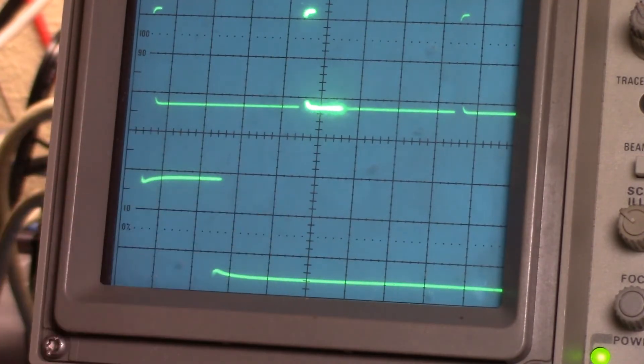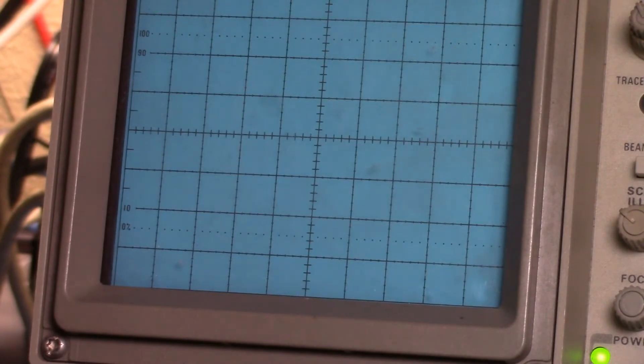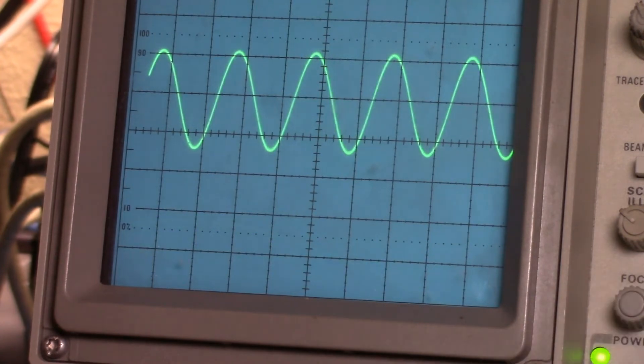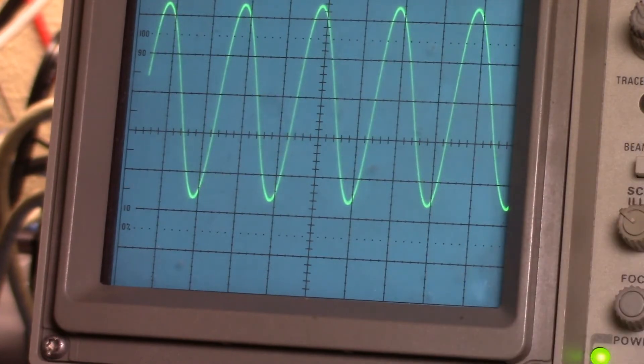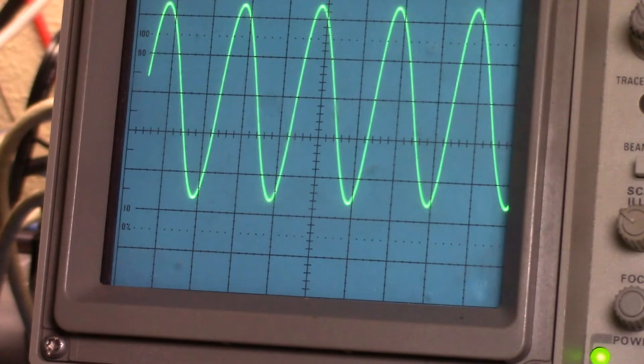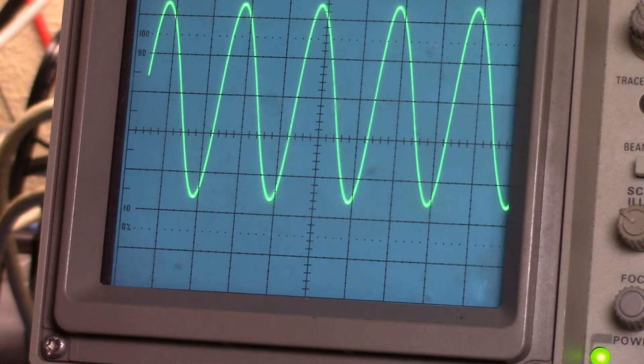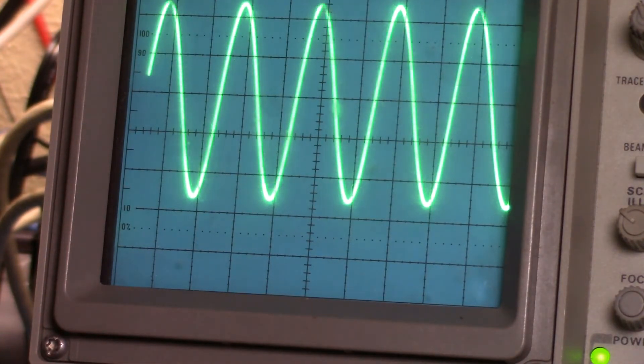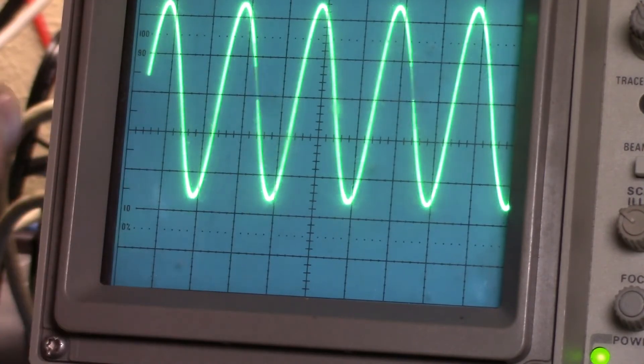Down here, we can see it's a little pulse coming in and that's what's going on. So if we put this back, if we put this back to our signal generator, you know, and then let's go back to A mode there. Let's step that back to one, get rid of our delay, you know, and now I reconnect that pulse up again. Now you'll see that little thing. Now, if you notice, when I take the signal off, you'll see the intensity drop and the gap disappears. Now, the reason for that is, is that as we looked at the actual pulse signal, you know, we're driving most of the pulse as negative. And then, let me get that locked in, there we go. And we're just simply getting a very short positive pulse that will blank the signal.